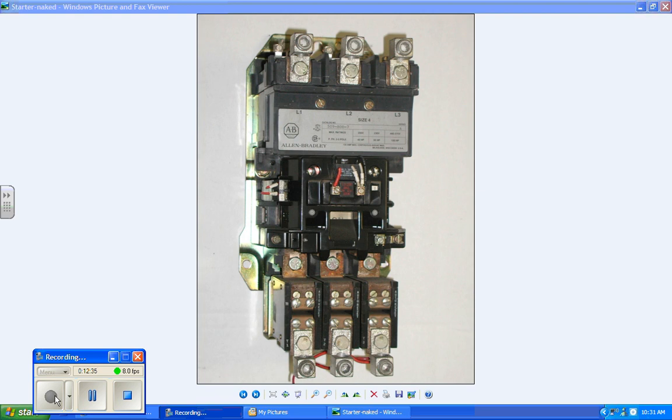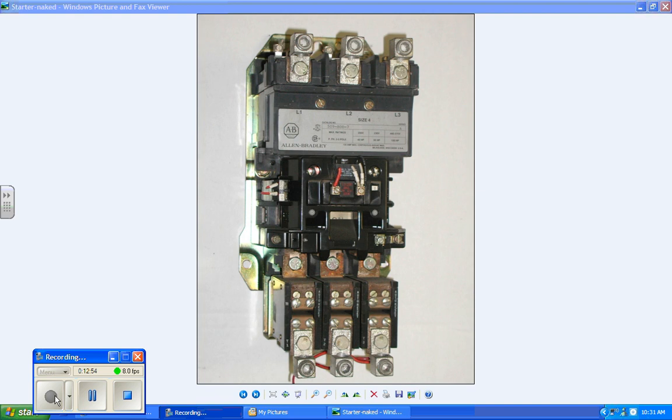A dashpot overload is one that allows for a large current to inrush, so it's actually a time delay on a start circuit. We have dashpot overloads in the lab, make sure you take a look at those. A dashpot uses, instead of air like a pneumatic time delay, hydraulic oil to create the time delay. So it's basically just a time delay device, but it's generally used for starting circuits to allow for the inrush current to happen.